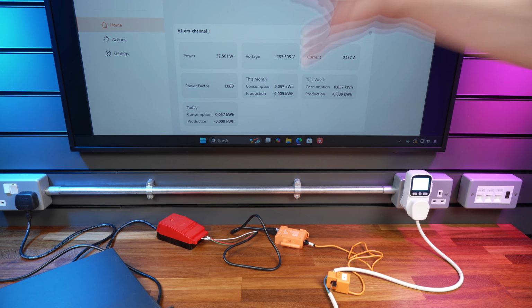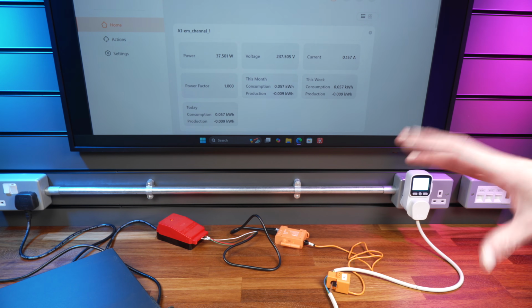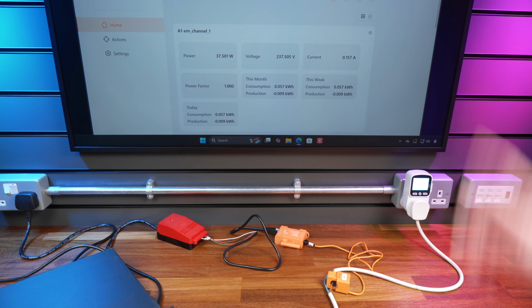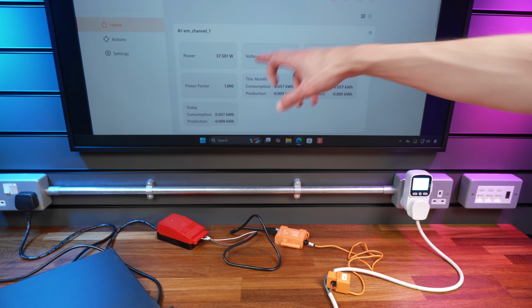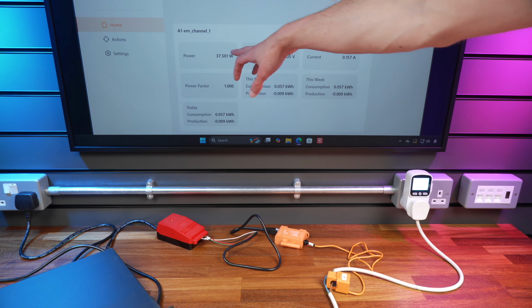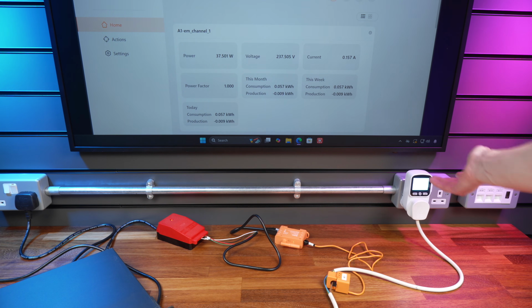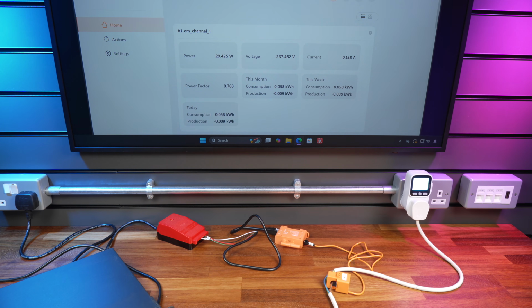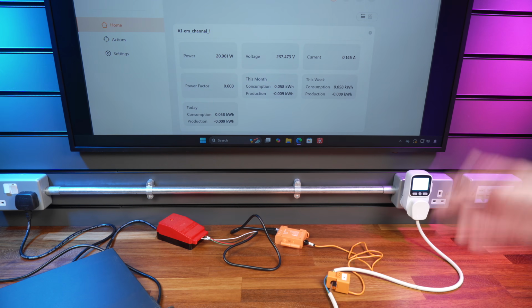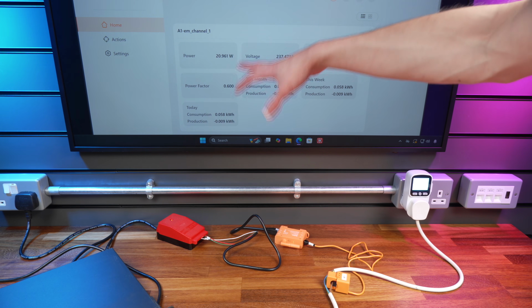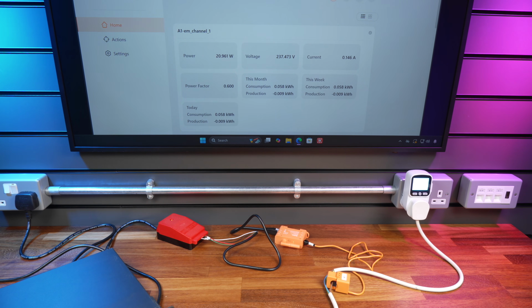But now, if you look at the Refoss interface, I'm getting some quite strange behaviour here. As you can see, right now, it's measuring a power factor of 1 and 37 watts, which is not right. This thing has a power factor of about 0.5 to 0.6. But then if we refresh the page, it will eventually change. So now we're getting 0.78 power factor, still a bit too high, but at least something. And then now we're getting 0.6 with 20 watts, which is about correct.